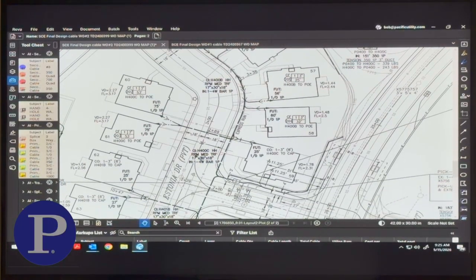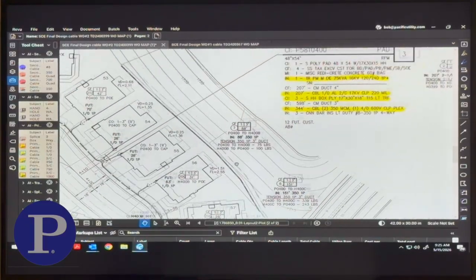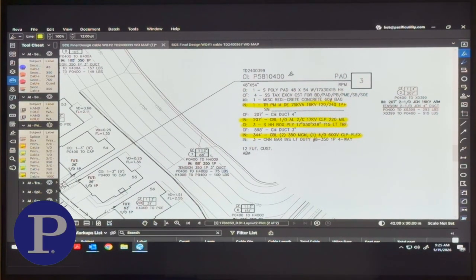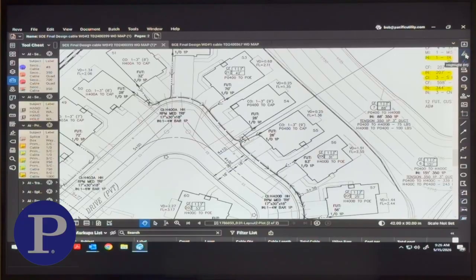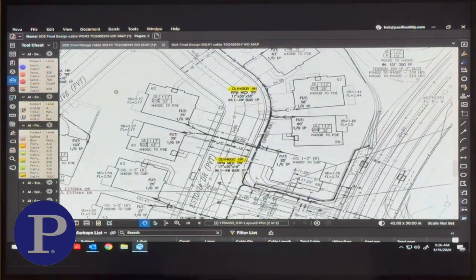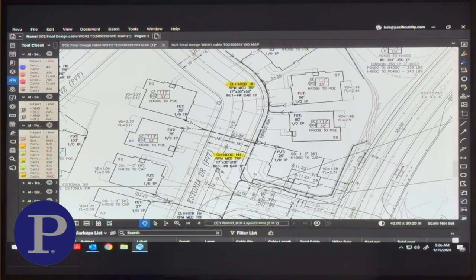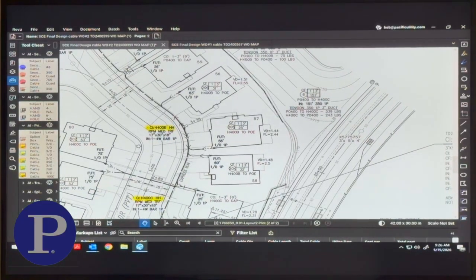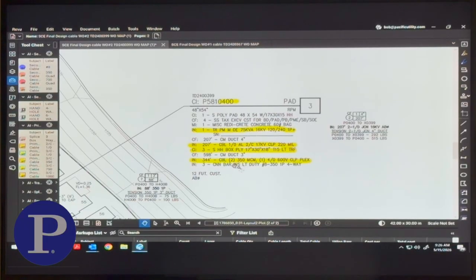How do we know that these are the handholes coming off of that transformer? If you look at the description next to the handhole, it'll show you this number right here, 400C. Now we know that this transformer is transformer 400. So if we go back down here, we've got handhole 400A, handhole 400B, and handhole 400C. That's our 3 handholes. So we're going to be pulling cable. We know that it's 350 cable to all 3 of these handholes.